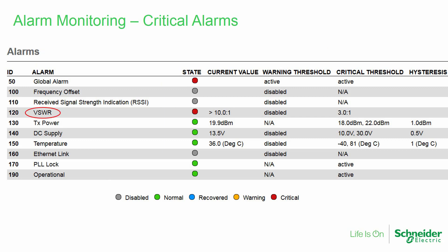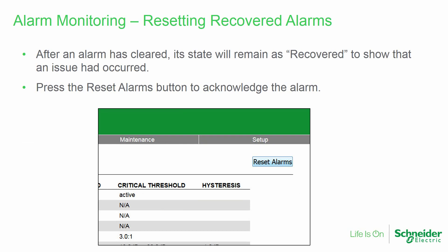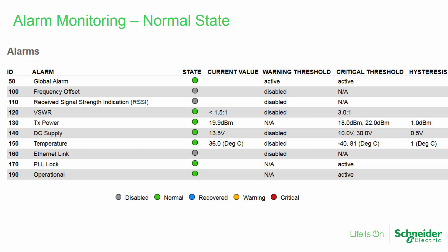Here it can be seen that a VSWR alarm has occurred. The state is red, or critical, with a current value of greater than 10 to 1 VSWR. Note that the critical threshold is 3 to 1, and that a global alarm condition occurs in such cases. The VSWR has since returned to normal with the value reported as less than 1.5 to 1 VSWR, and the alarm state is now showing as blue, or recovered. After an alarm has cleared, its state will remain displayed as recovered to show that an issue has occurred. The user may then press the reset alarms button on the alarms and events page to acknowledge having seen the alarm. Once the reset alarms button has been pressed, presuming no other alarms are currently active, the alarms display will appear with some alarms reported as disabled, including frequency offset and RSSI, though warning values may be enabled if desired. All other conditions show as green or normal.